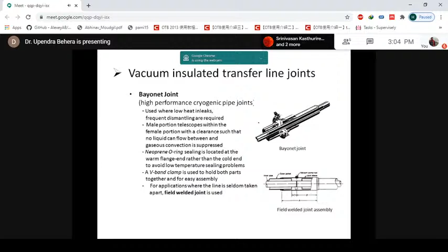And for applications where the lines are seldom taken apart, these field weld joints are done. This is the vacuum line ending here, and the other one is ending here at the extension, and they can cut open here for repair and everything. This can be done in the field. They can directly join it if it is not used for dismantling again and again; this type of vacuum joints is used for vacuum insulated transfer lines. Okay, these are some fundamental aspects which I have told on transfer lines.